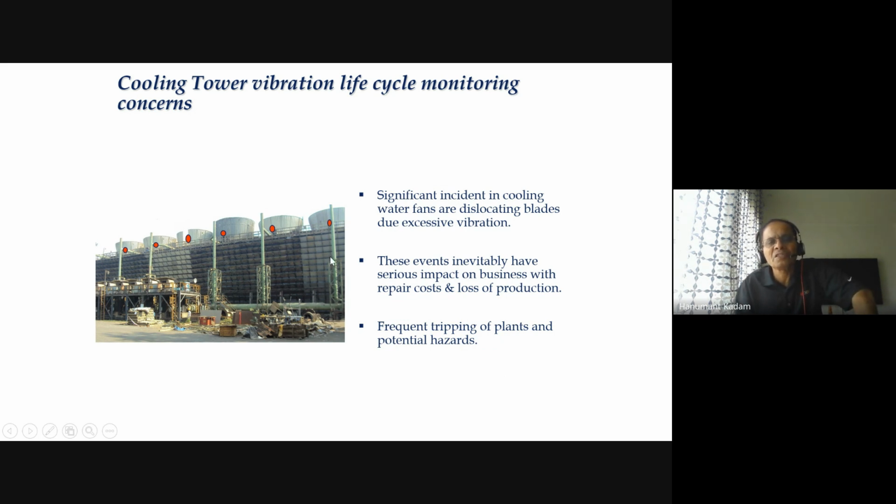So you see these cooling towers, and the water here is coming down and is cooled using a fan on top. On this tray you can see the fan is there and the fan is rotating. Most of the structure is wooden, so always because of the fan and the height it vibrates. So operators or maintenance staff mainly ignore going there, and we miss those measurements.